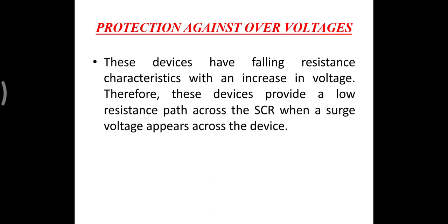So this is the important point we have to remember. The characteristic of these voltage clamping devices is falling resistance with increasing voltage. That means with increasing voltage the resistance is reduced, which provides conduction for the high voltages. Okay? In this way we provide protection for the SCRs.